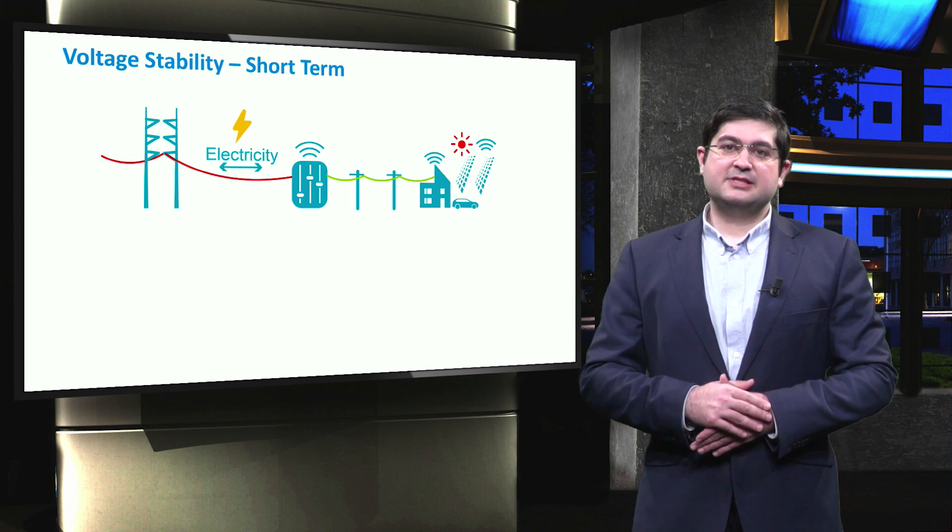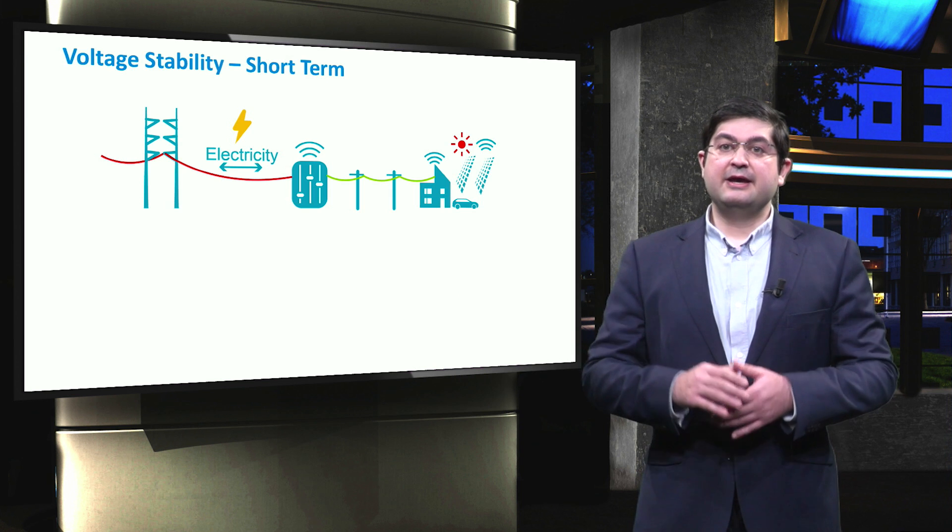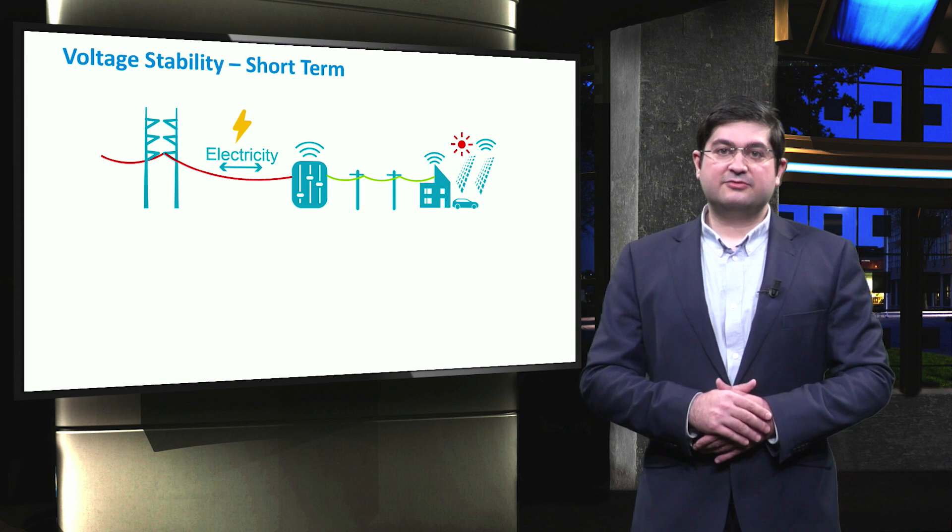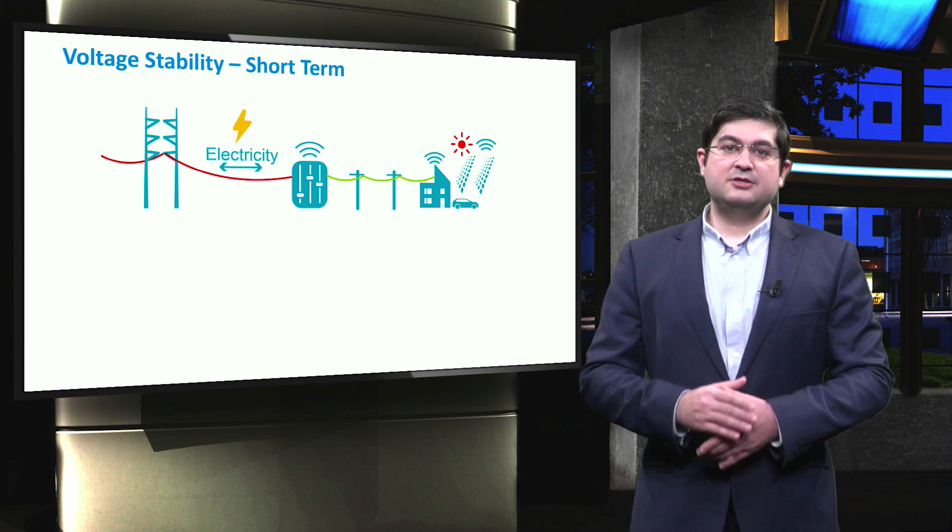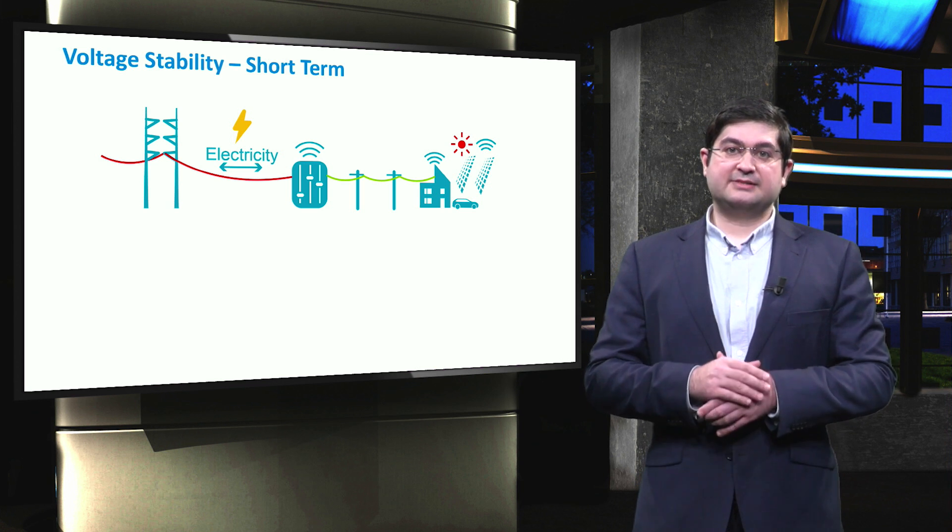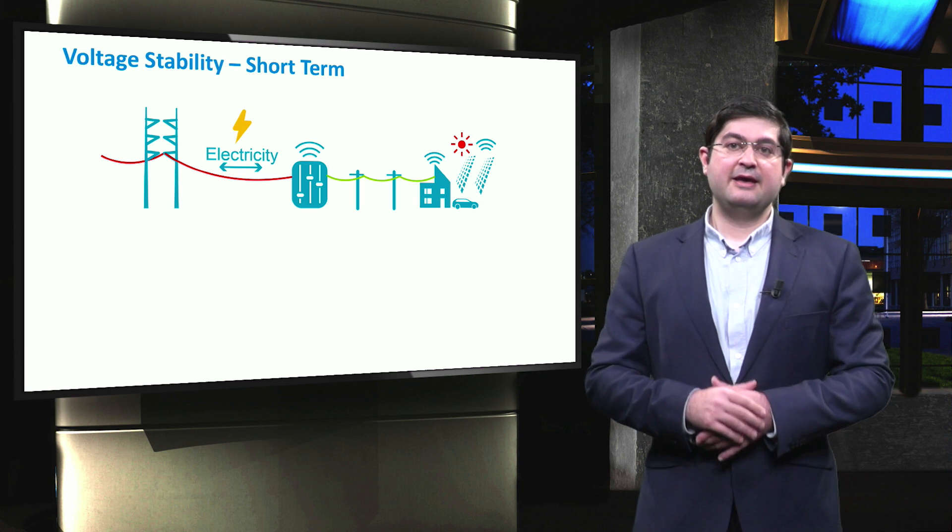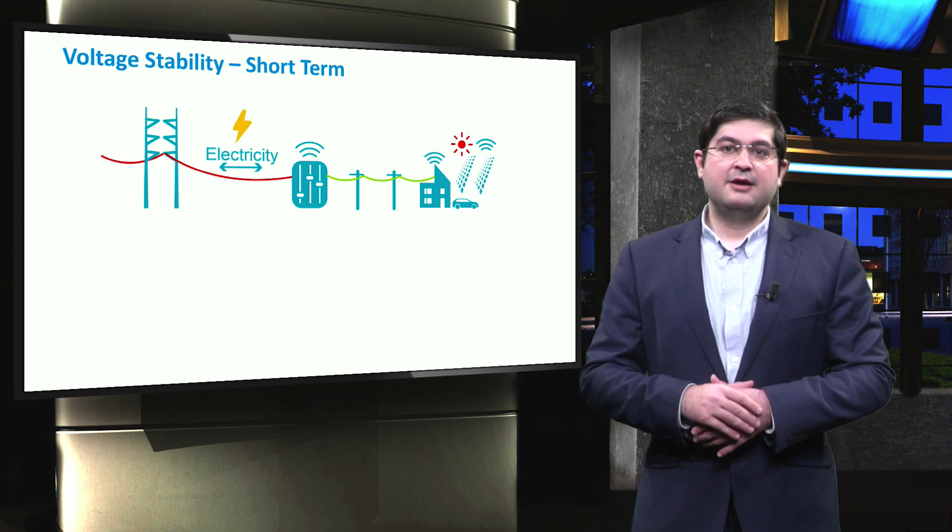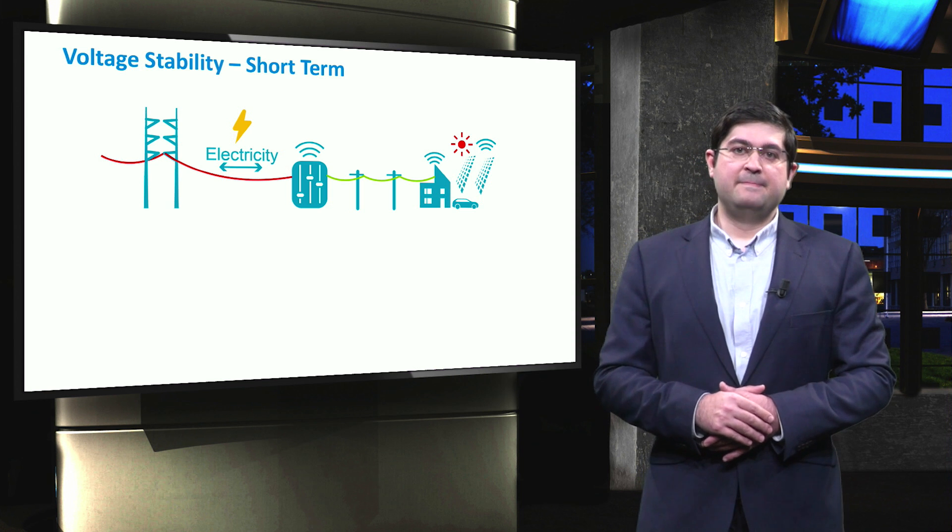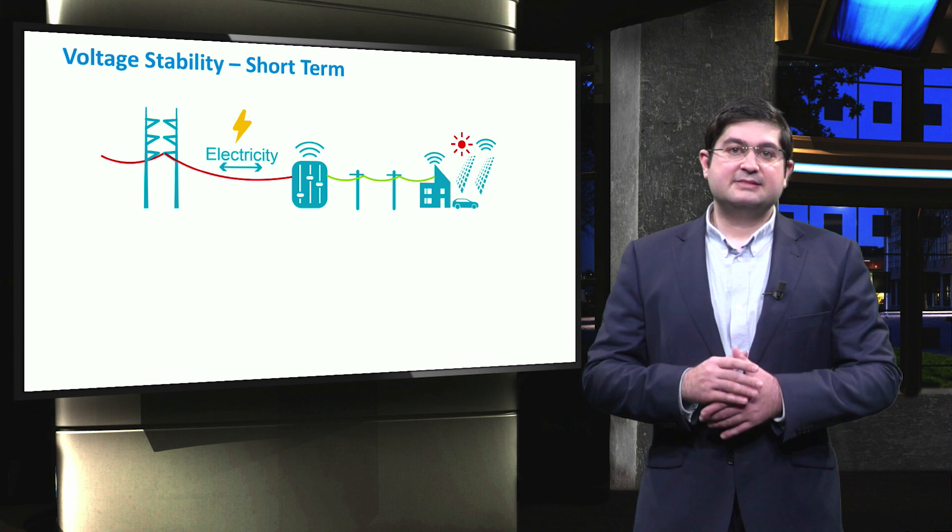It is worth emphasizing that the classification of stability in microgrid is different than the one of traditional power systems due to several reasons. If the microgrid is connected to the external grid, then obviously the size of microgrid is relatively small compared to the whole system. Therefore, the frequency of microgrid is dominantly set by the grid.